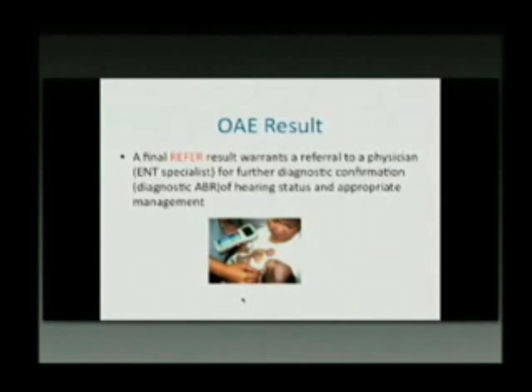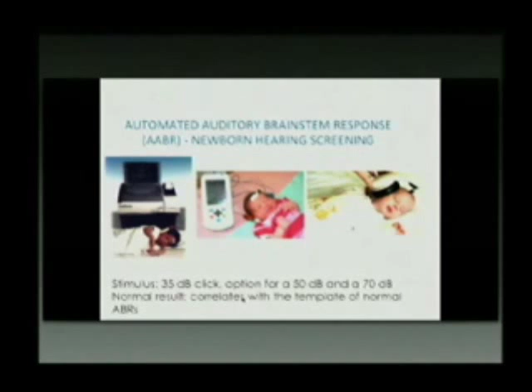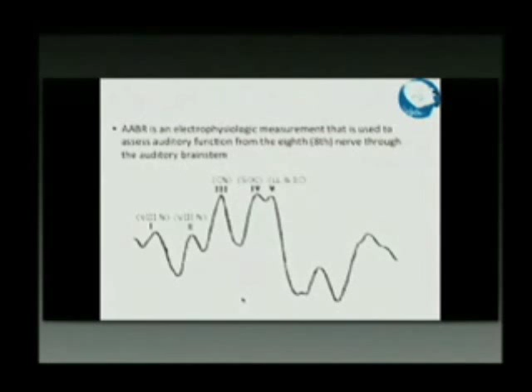diagnosis. Now, the other test is your automated auditory brainstem response test. You can see on the left side, you have this big bulky machine, and to the present time on the right, where electrodes are sometimes not needed anymore. The AABR is an electrophysiologic measurement that is used to assess auditory function from the 8th nerve through the auditory brainstem. Generally, electrodes are placed on the forehead, mastoid, and nape of neck. And like I mentioned previously, in some devices, you don't need these electrodes anymore. Click stimulus is presented at 35 decibels via disposable earphones.